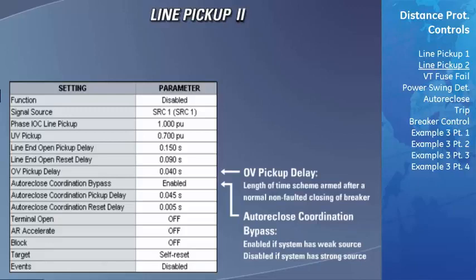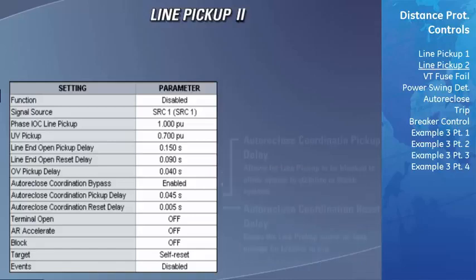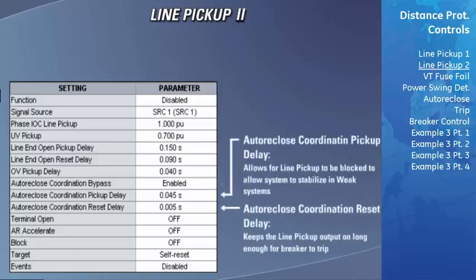You'll remember that for weak systems, the phase IOC line pickup setting was set below the normal inrush current level. If the line pickup element is used in this format, an extra delay is added to the operation of the element to allow the system to stabilize itself in unfaulted reclosing situations. The auto-reclose coordination bypass is normally enabled if the line pickup element is being used on weak systems and disabled if it is being used on a strong system. The auto-reclose coordination pickup delay will only be used if the auto-reclose coordination bypass setting is set to enabled.